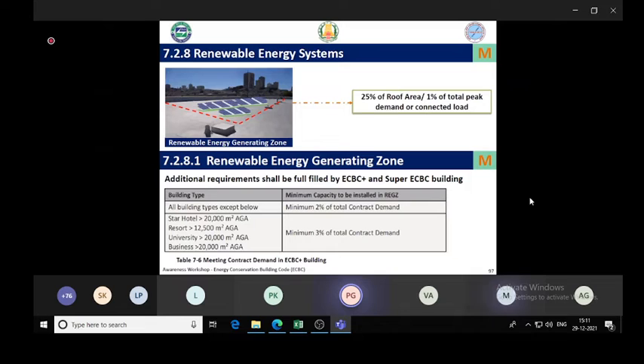Okay, and this is the final part in the electrical section, which is renewable energy systems. It is mandatory to allocate space for renewable energy on the roof. We need not install the renewable energy system, but space should be allocated. So space of 25% of the roof area should be allocated, or 1% of the total peak demand. That is sufficient space to meet 1% of the total peak demand. Either of these should be allocated.